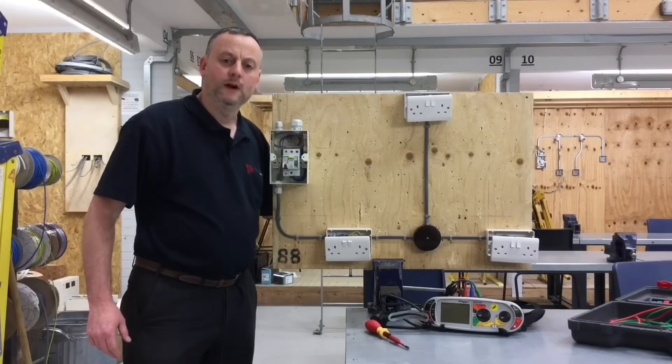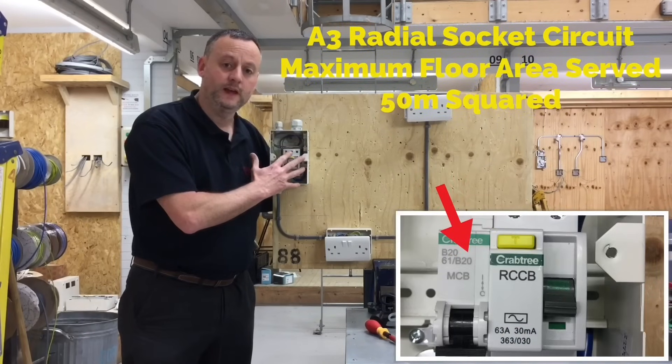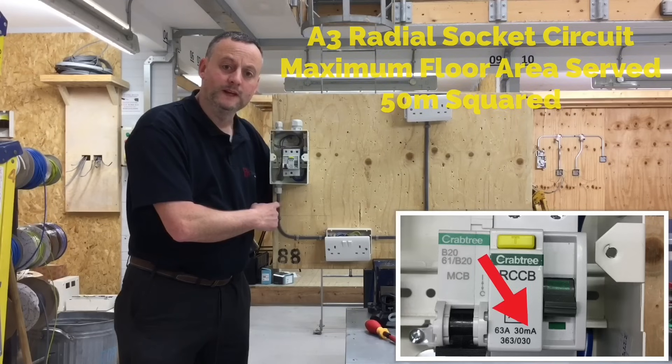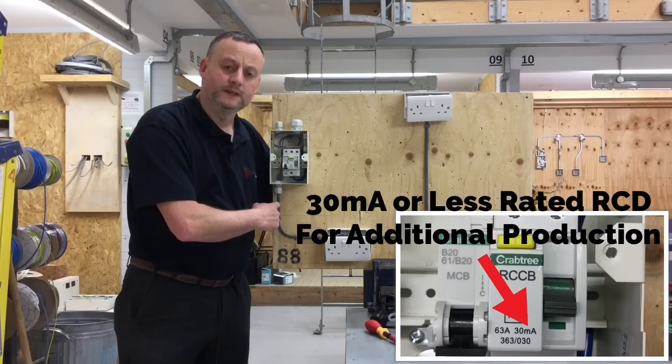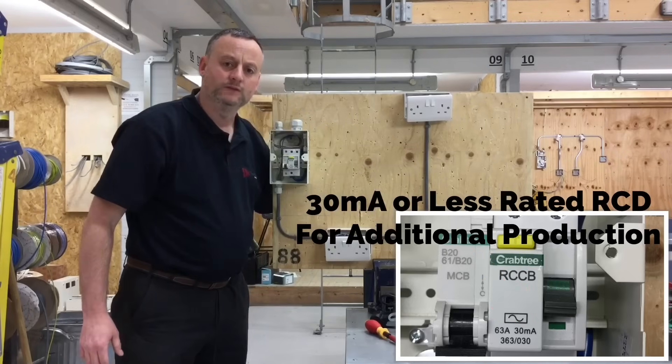Learners are up to week 12 of their studies and we've done a very basic A3 radial. We've got a 20 amp MCB in the consumer unit, wired in 2.5 millimetre squared twin and CPC cable, with three socket outlets wired in the form of an A3 radial.